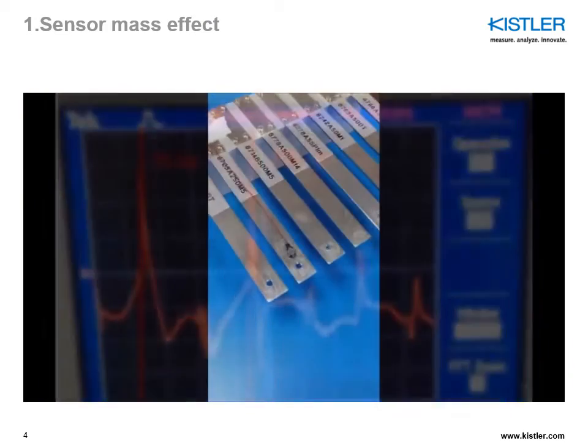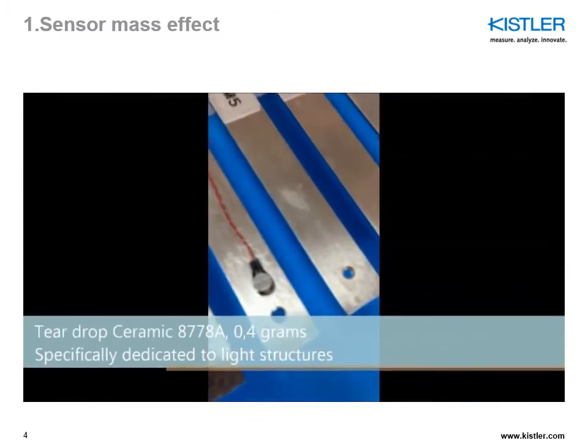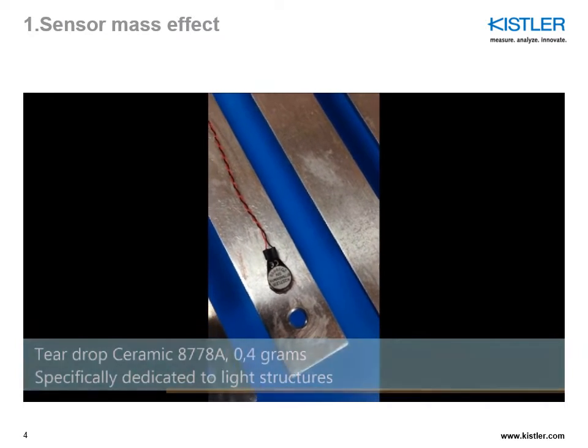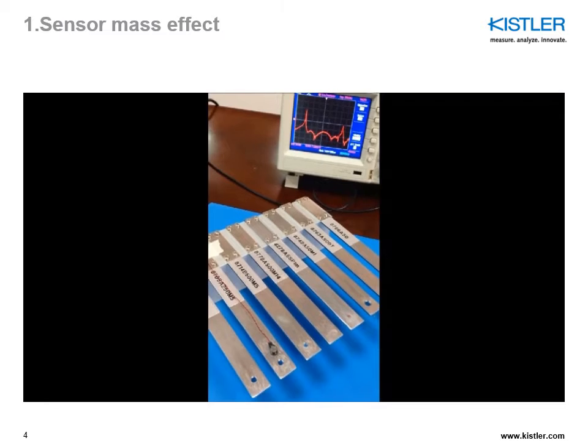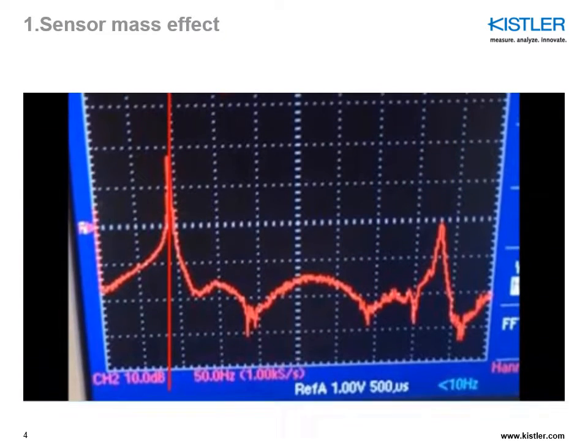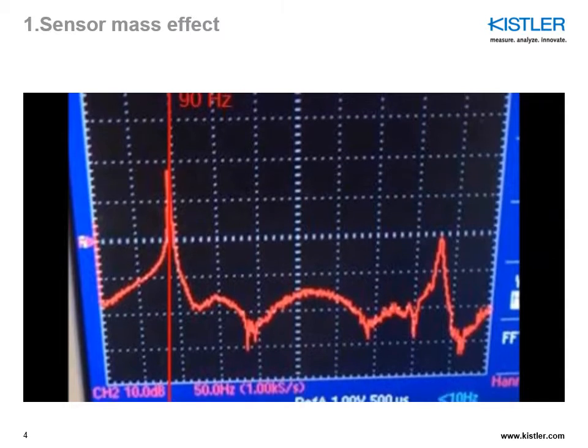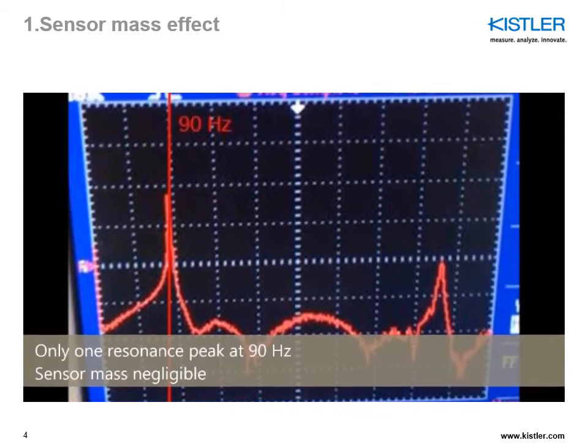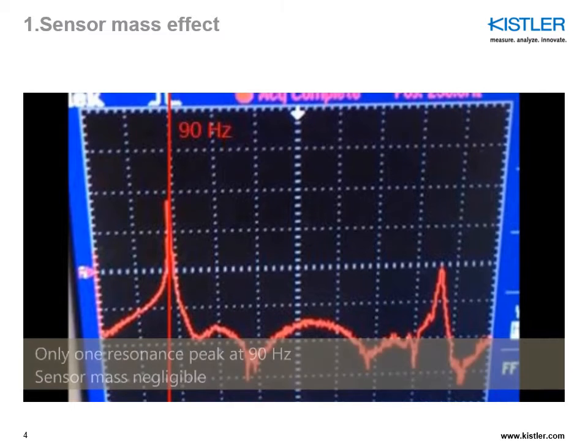A lighter sensor is needed. We are now going to use one of our teardrop sensors, the 8778A, which is 0.4 grams. With this sensor, the first peak shifts higher to 90 Hz and the next peak is much lower and further away. The sensor mass here can be assumed as negligible.